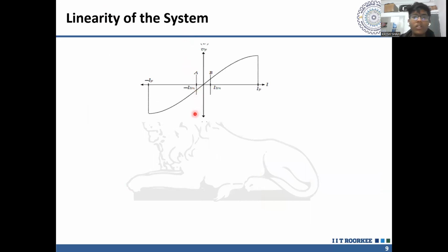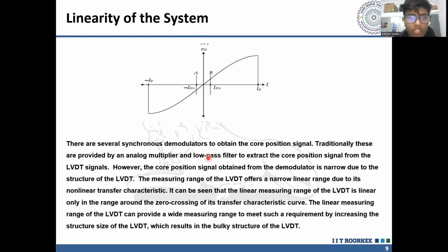Linearity of the system, as we were talking about. Here we had this particular characteristic graph of the LVDT, and only this small range is where we can get a linear response of the LVDT displacement, which is very useful in doing analysis of multiple things. There are several synchronous demodulators to obtain the core position signal. So this signal E out is sent to a demodulator to get the core position of the signal. Traditionally, this is done by an analog multiplier and low pass filters to extract the core position signal. However, the range of this is very narrow due to the structure of the LVDT. If you want to increase the range, you have to increase the size of the LVDT, which is not possible in some of the applications that we mentioned earlier.